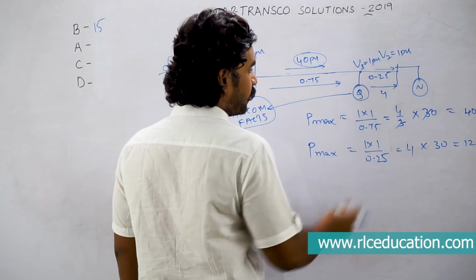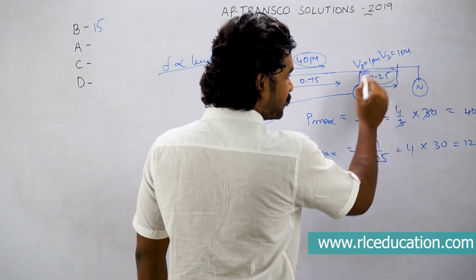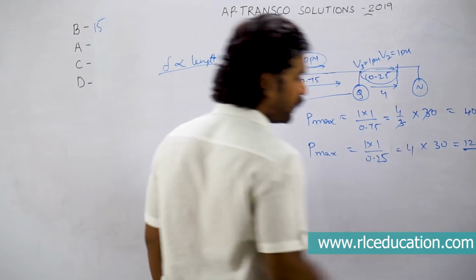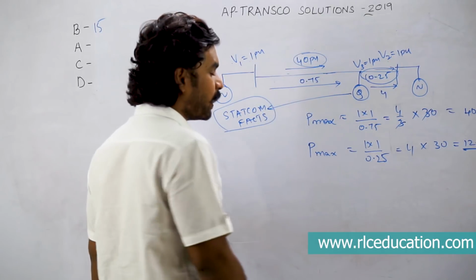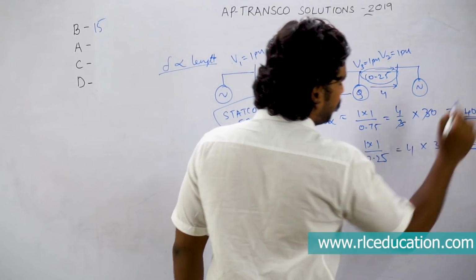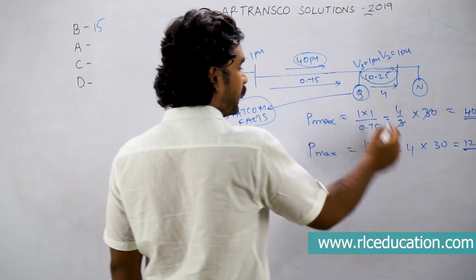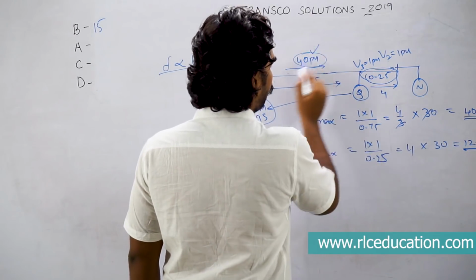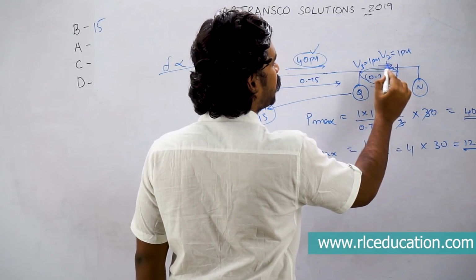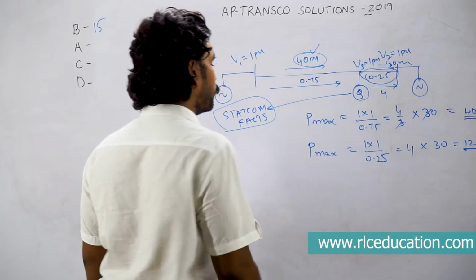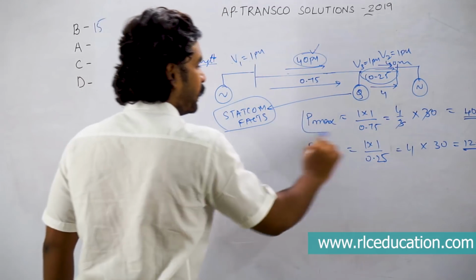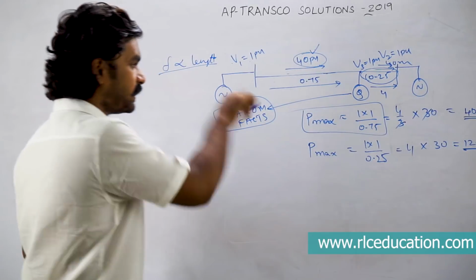So even though the capacity of this portion of the line is to carry 120 megawatts, it will not carry 120 megawatts — it will just carry 40 megawatts only. Understood? That is the maximum capacity. But since 40 megawatts has been transferred, here also 40 megawatts will prevail in the circuit. So this will be your actual maximum power transfer in this case.